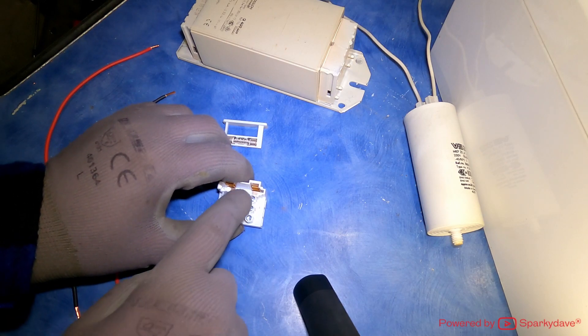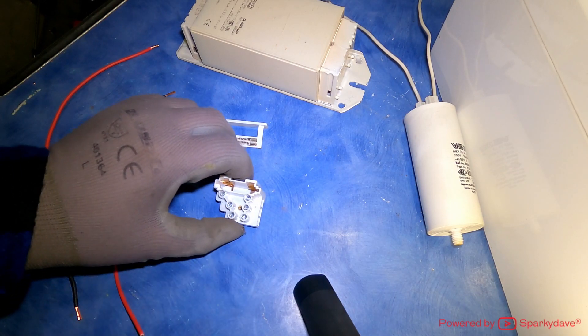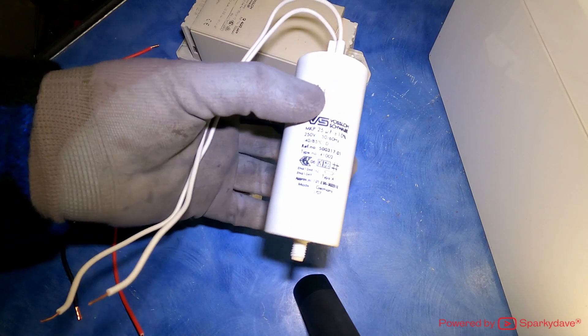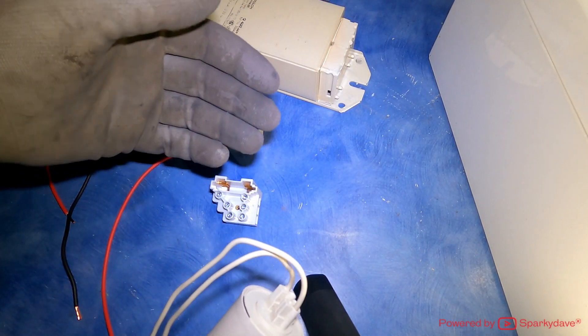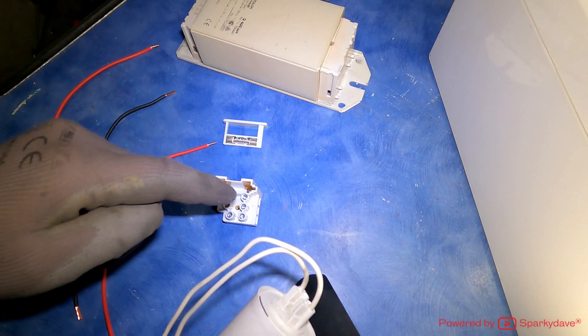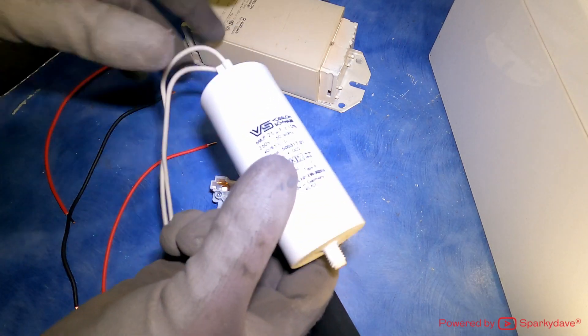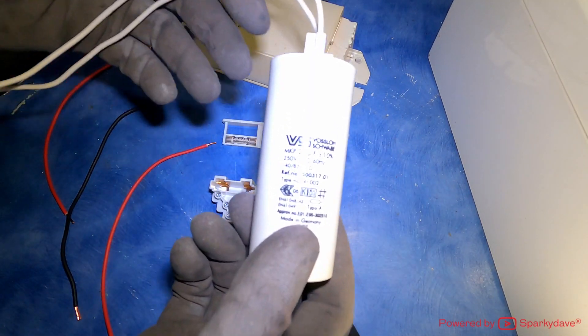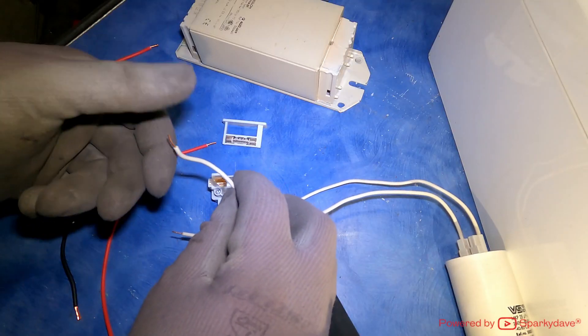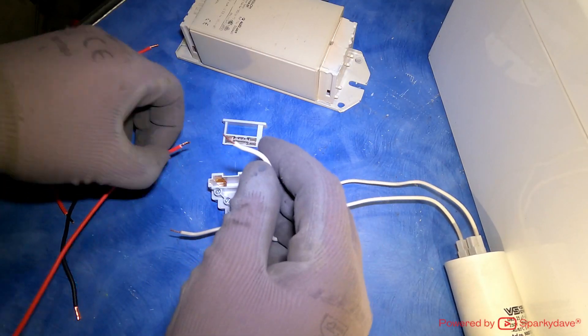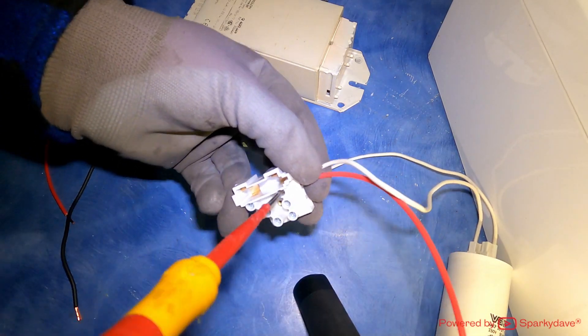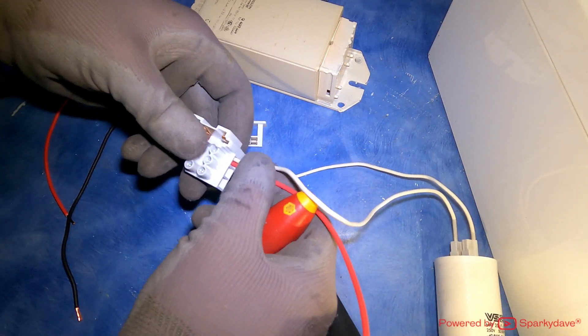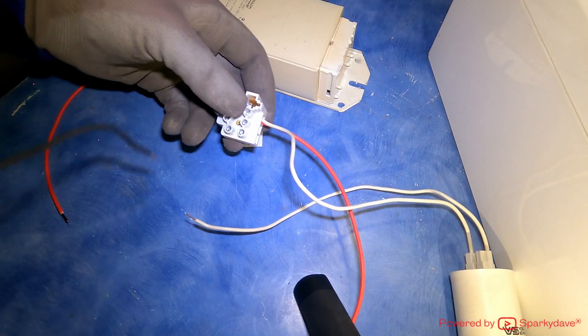Generally your capacitors are going to sit in parallel with the circuit. That means one end will be in the phase and one end will be in the neutral. So this capacitor can be fit off right at the start. One of the tails we're going to put in with our phase cable and screw them in together, and the other end goes with our neutral cable. So that is the capacitor in the circuit.